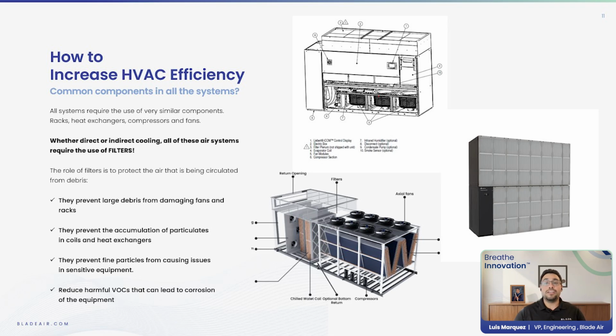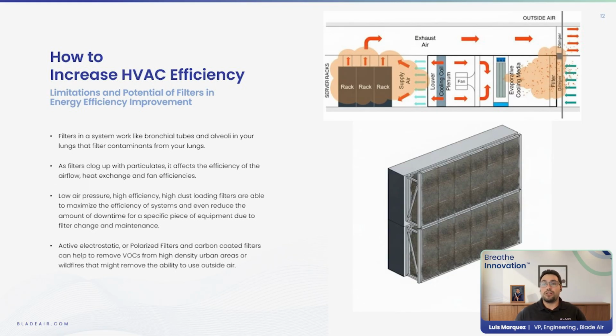One, to help prevent large debris from damaging the fans and other components. They help prevent particulates and other pollutants from forming on the coils, keeping the heat exchange optimal. And then they reduce fine particulates that can cause issues for critical and sensitive equipment. And certain types of filters can also help to reduce harmful VOCs, which can lead to corrosion of the equipment. Filters work much like bronchial tubes and alveoli in your lungs, clearing the air from contaminants. As the filters clog up, it reduces the efficiency of the airflow, the heat exchange, and the ability of the fans to operate efficiently. It's like their system is getting asthma, for lack of a better term.